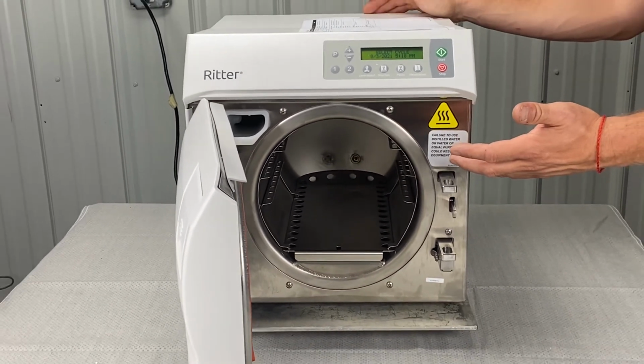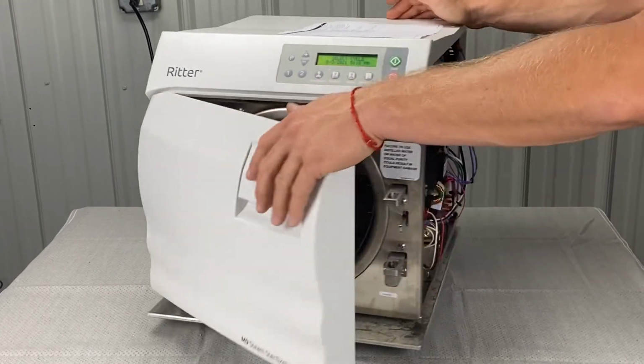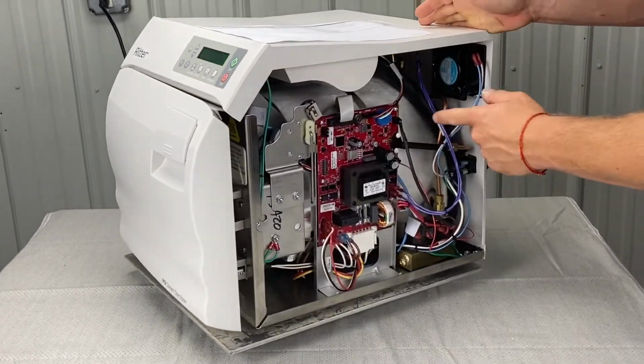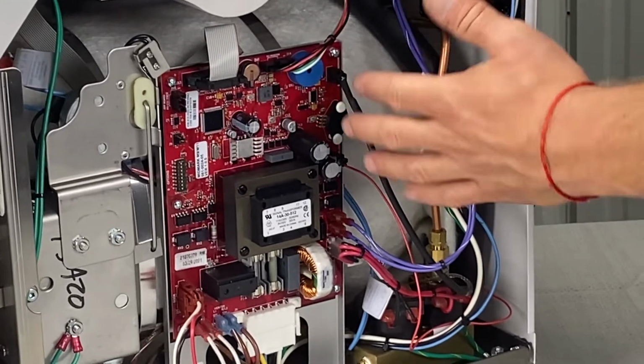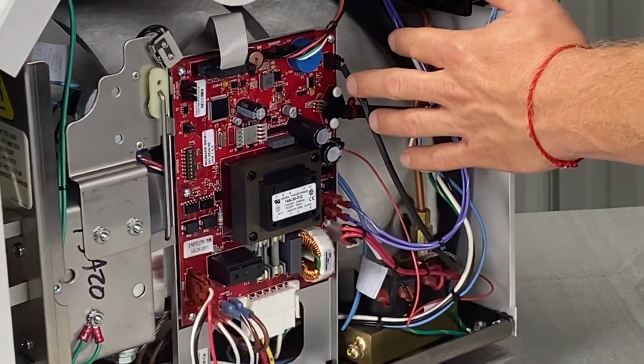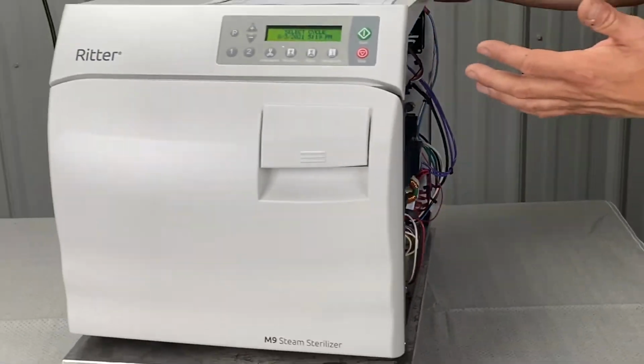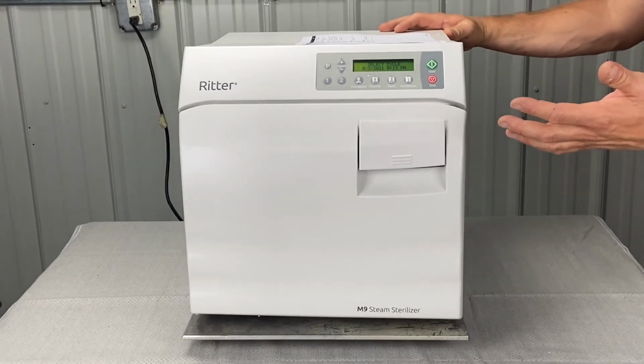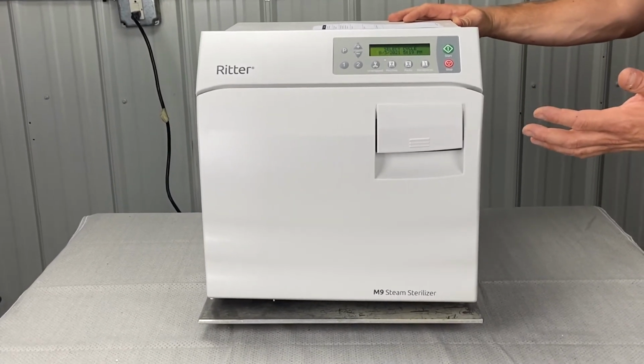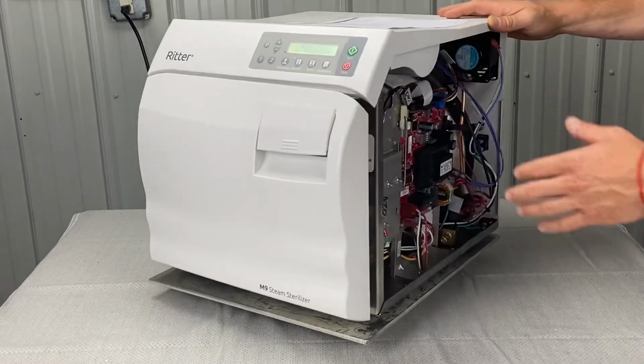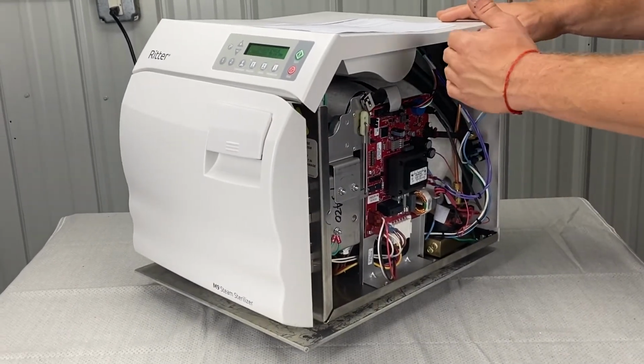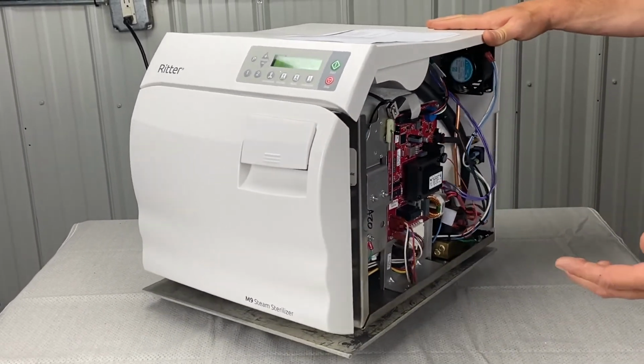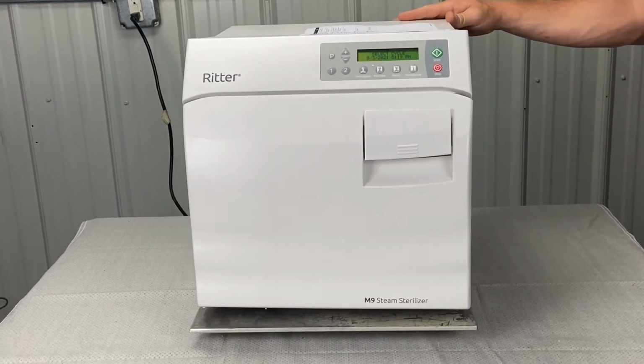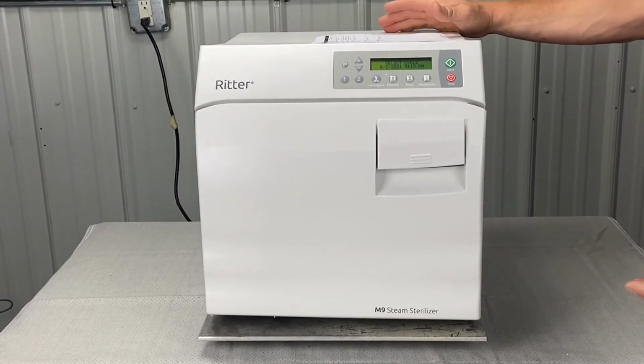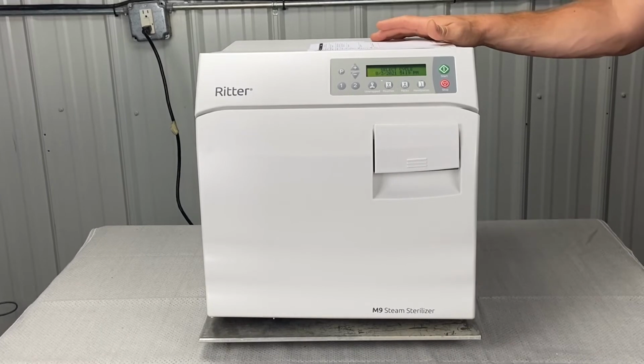And then you can perform a temp sensor test with the ohm meter and the temp sensor. Call us before you do that. You're going to need a multimeter. There's another, you can perform a temperature sensor supply voltage test. Again, you're going to need a multimeter and some patience, but that could possibly reveal that the main PC board is bad. I'll be honest, I don't see that happen too much with this particular error code or temp sensors for that matter.